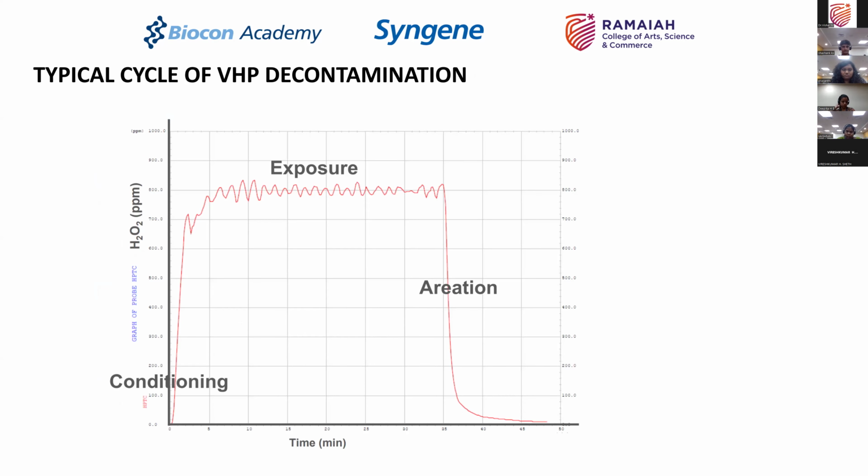Okay, this is what happens. You have the conditioning, you have the exposure, and then you have the aeration. So the value of the H2O2 goes up, and then it goes up to, in this case, a dosage rate of around 800 plus or minus something.